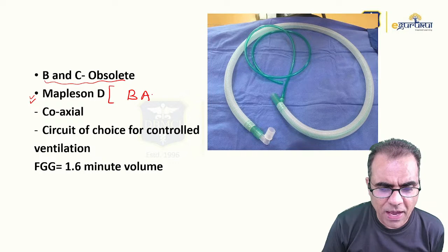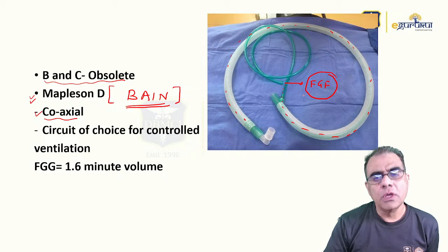He incorporated an inner tube into this outer tube. You can see the inner tube going all along the length, and this inner tube will be attached to the anesthesia machine. So fresh gas flow will come through the inner tube, and expiratory gases through the outer tube, so there will not be any mixing.